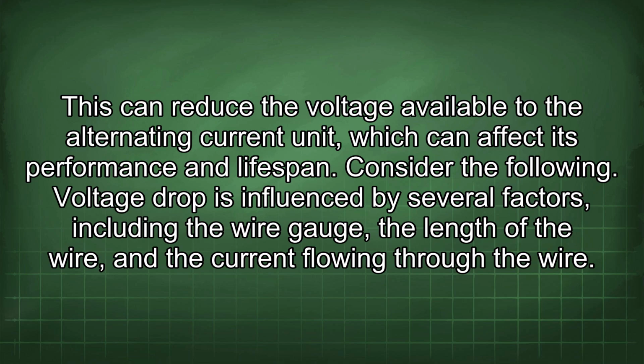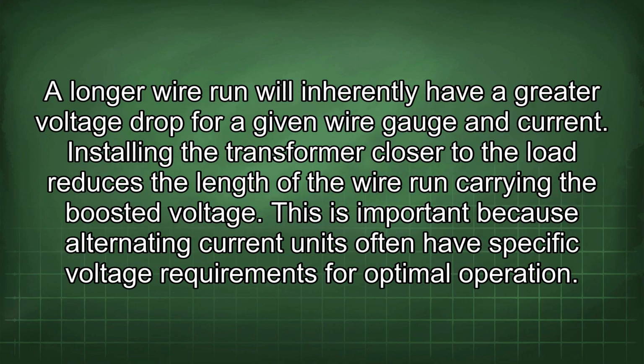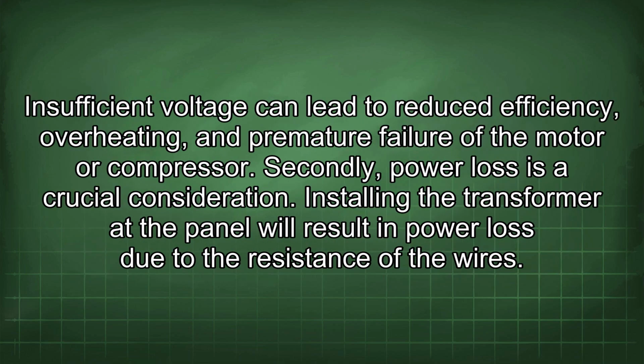Consider the following. Voltage drop is influenced by several factors, including the wire gauge, the length of the wire, and the current flowing through the wire. A longer wire run will inherently have a greater voltage drop for a given wire gauge and current. Installing the transformer closer to the load reduces the length of the wire run carrying the boosted voltage. This is important because alternating current units often have specific voltage requirements for optimal operation. Insufficient voltage can lead to reduced efficiency, overheating, and premature failure of the motor or compressor.